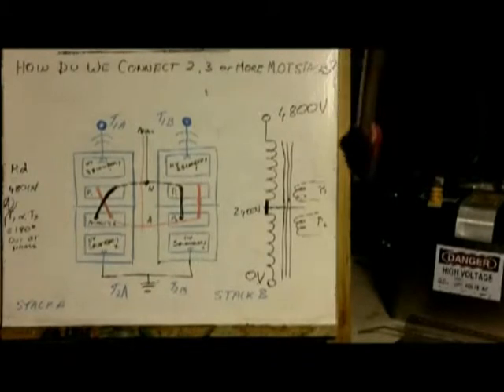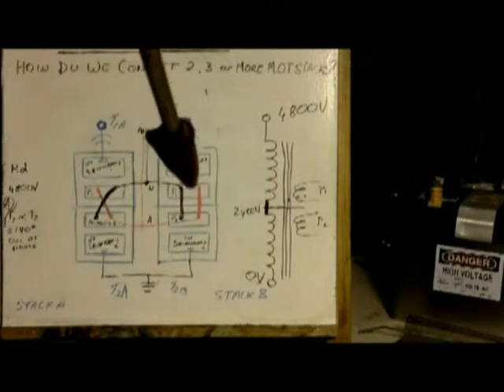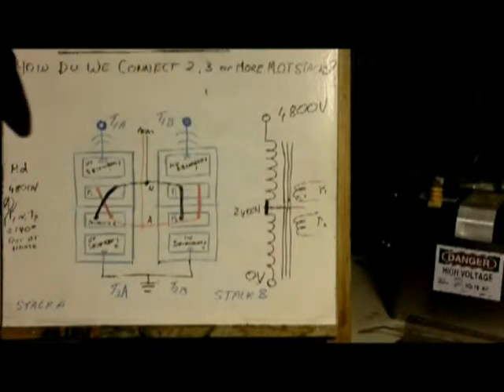So for insulation purposes, you probably don't really need any mineral oil. Of course, unless you're planning to draw excessive loads and you really want to get really good heat distribution. And if you do that, that will be totally up to you. It probably does help as well to insulate it with mineral oil, just adds to insulation. But if you use proper high voltage techniques, it's not entirely necessary. Like I said, these units are actually designed for a potential difference from the winding to the core of 2400. Probably in actuality it'd be a lot more than that, but at least you know you're safe.